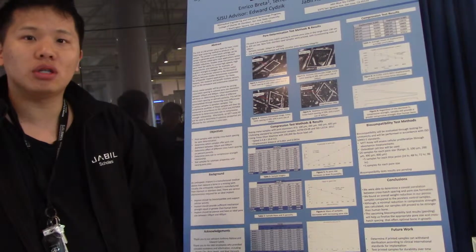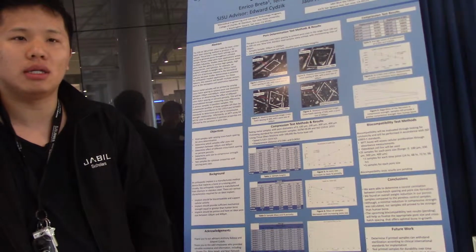Now, one thing in the future that we hope to be able to do is to verify the porosity throughout the sample in thicker samples, because one thing we couldn't do here was that, because 316L is such a dense material, we couldn't use technology like CT and X-ray to get a better sense of what the porosity might be like in the center of a thicker sample, which is important because for implant fixation, the interconnectedness of the pores is an important factor for the fixation to be reliable.